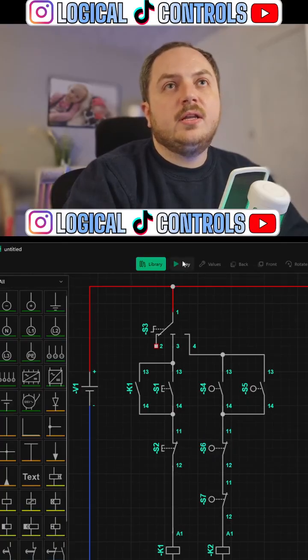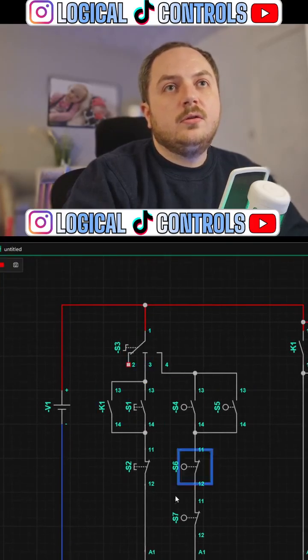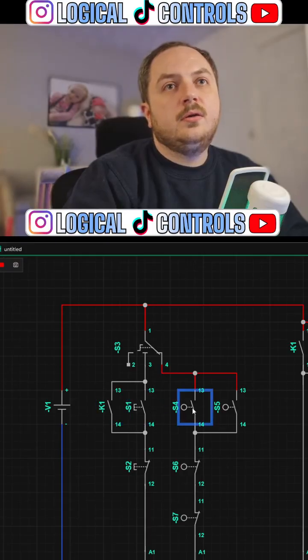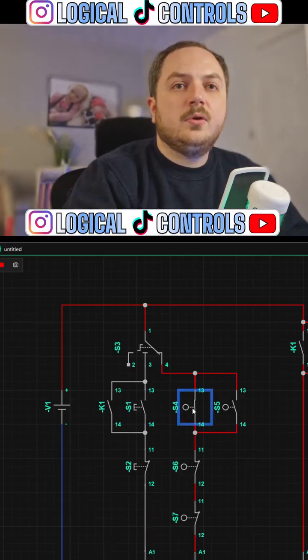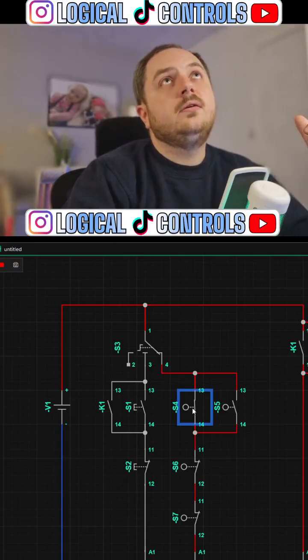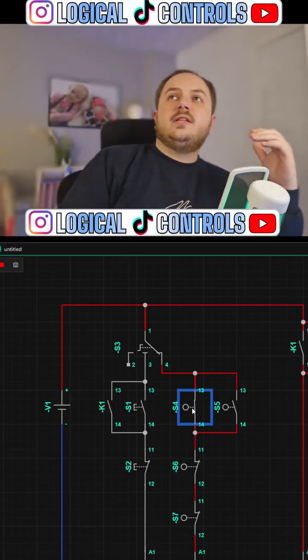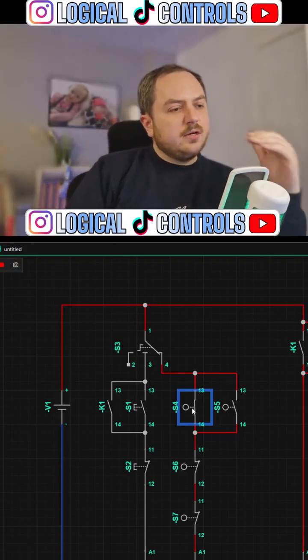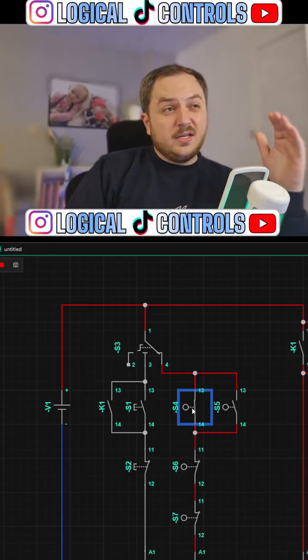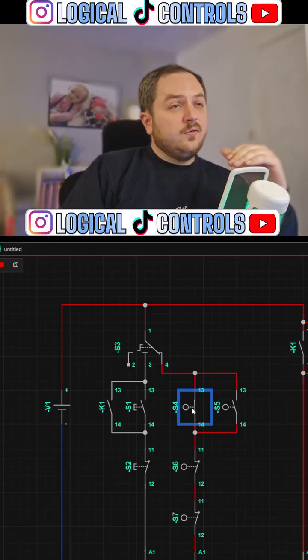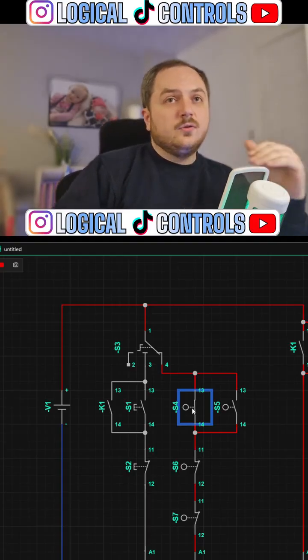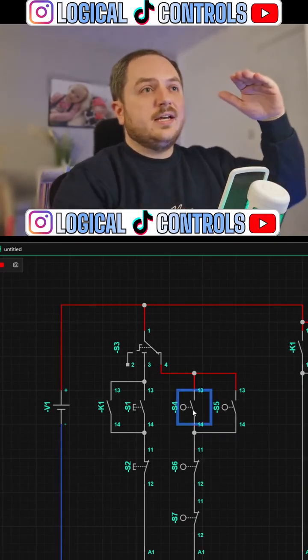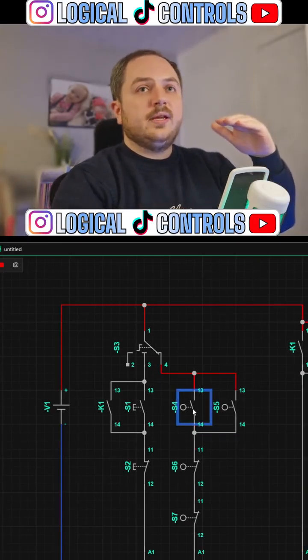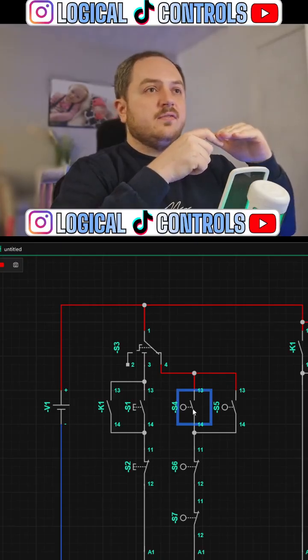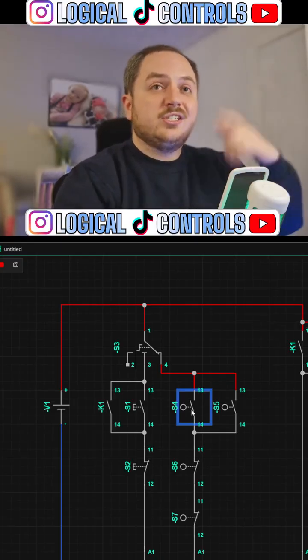They definitely want to... right, let me put it in run, let me put it in auto. If either of them make... okay, so what I've done instead of - I think I originally said make on rise, I can't remember - but what it is now is make on fall. So if the liquid level halfway in the tank starts to drop, it will then make that float switch, that low level float switch, and start the pump.